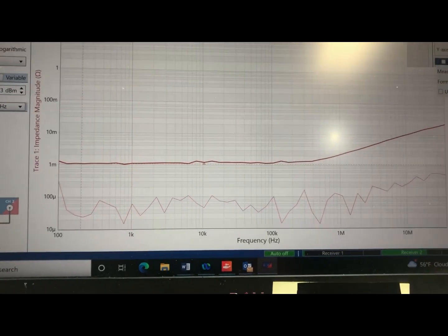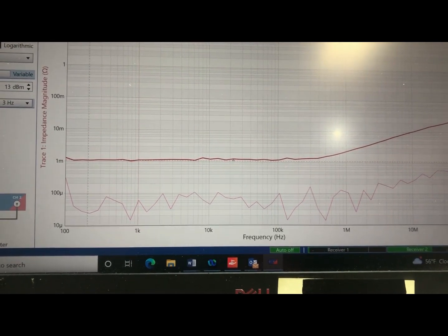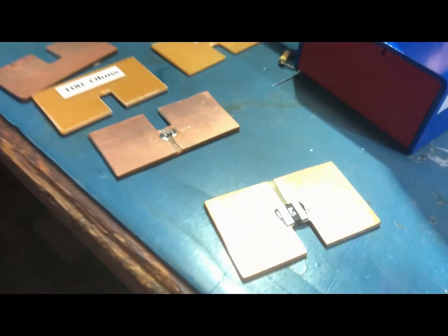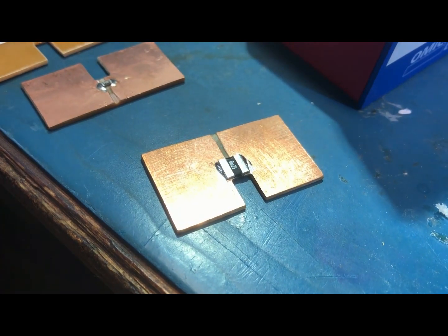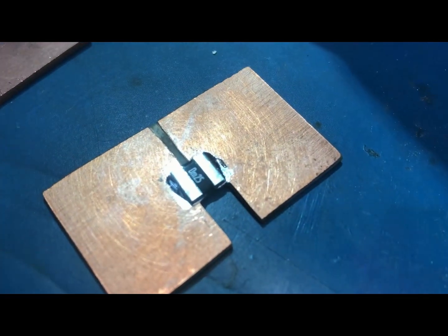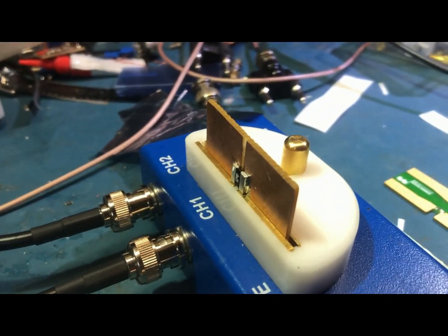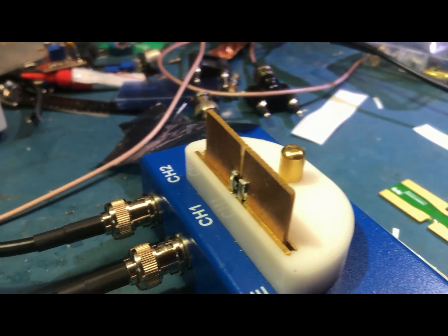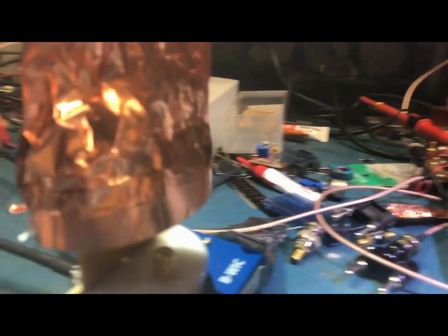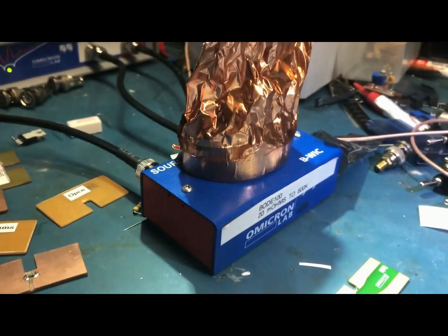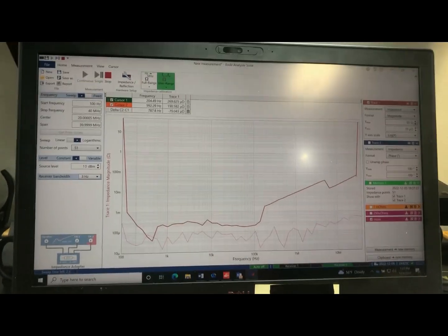Okay, so let's see. I have one more measurement. This one is a 250 micro-ohm. Let's see if it'll fix it. Okay, so here I have the 250 micro-ohm resistor in its PCB jig. I'll go ahead and put the Faraday shield. Okay, so here is the measurement.